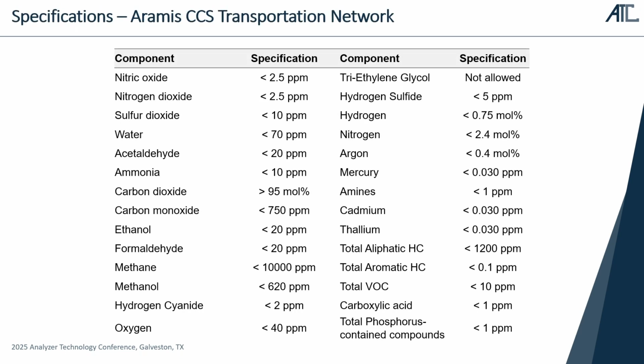So here's a typical specification that you will see. This is a specification from Aramis in the Netherlands. Aramis is tasked with designing the transportation network for Porthos out of the Port of Rotterdam, also in the Netherlands. And you can see here the component list, compared to a majority of the US specifications, is a lot more stringent. This was selected for the study because at the time it had the lowest requirement for NOx.